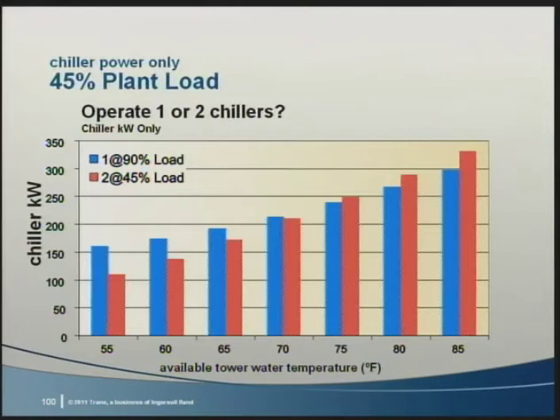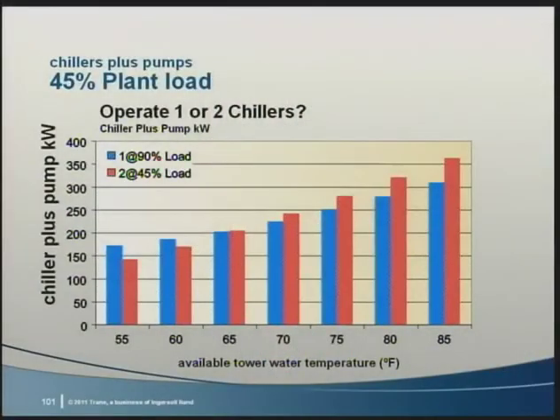Unmistakably, until the tower water temperature falls below 70 degrees, 1 variable speed chiller operating at 90% load consumes less power than 2 equally loaded variable speed chillers. It's worth emphasizing that this comparison does what IPLV cannot: compare like chillers in a like condition, apples to apples, if you will. In addition, this is only chiller energy used. Remember, these cold tower water temperature conditions may not be economically attained. Also, pump and tower energy were not included in the previous slide. Assuming a VPF system on the chilled water side, but constant speed condenser water pumps, until the tower temperature goes below 65 degrees, only 1 chiller should operate.